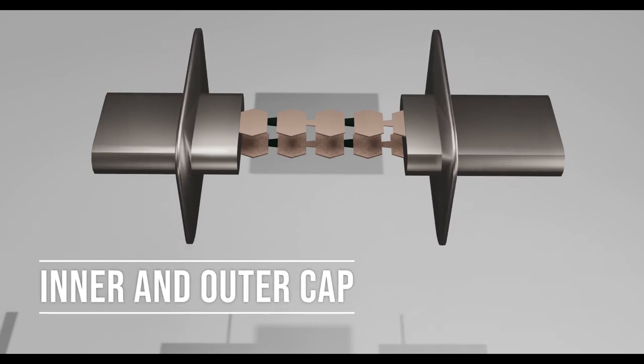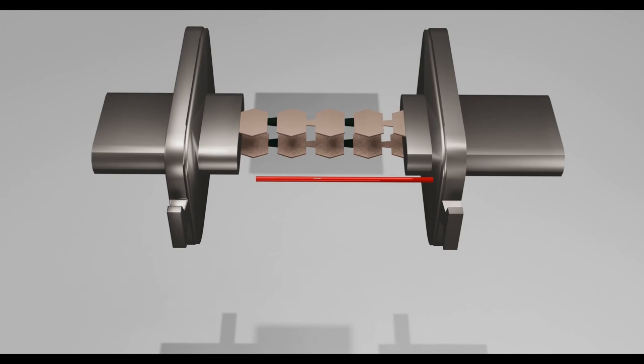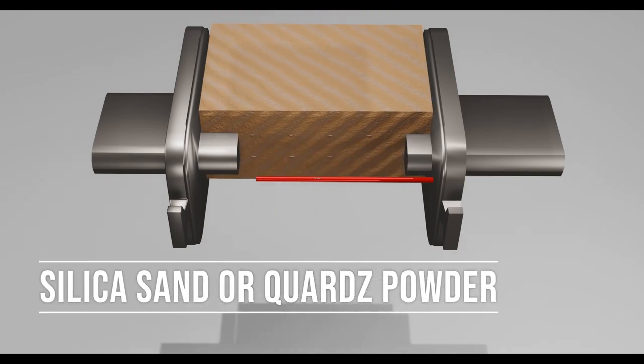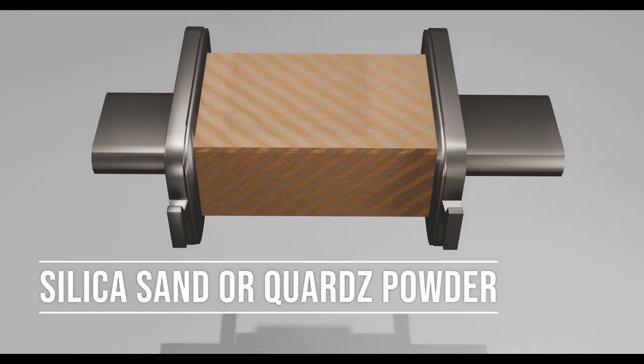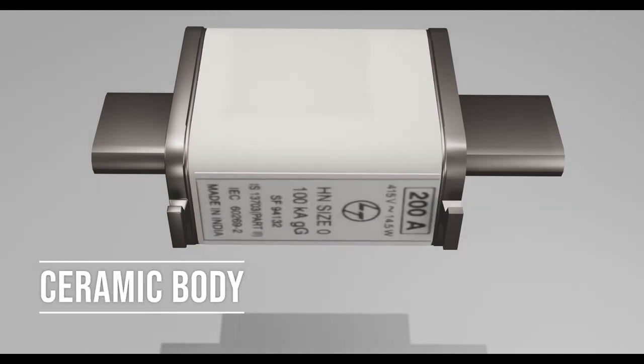see here, which is made up of brass material. This red element is a fuse blown indication flag. After that, this whole assembly is covered with silica sand or quartz powder, which is used to extinguish the arc. Lastly, the outer body is mounted like this, which is made up of ceramic material.